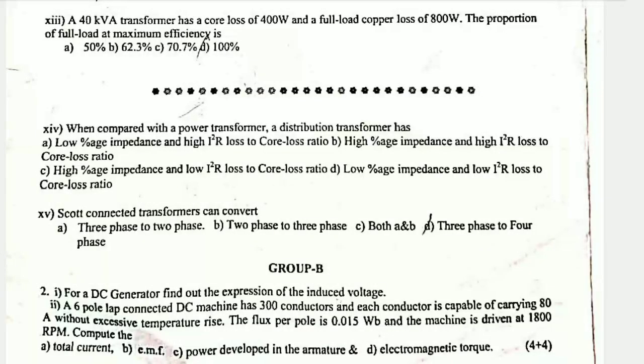Question 14: Comparing power transformers and distribution transformers, the key difference is in percentage impedance and core loss ratio. Distribution transformers have low percentage impedance and high core loss ratio, while power transformers have high percentage impedance and low core loss ratio. Question 15: A Scott-connected transformer can convert 3-phase to 2-phase.